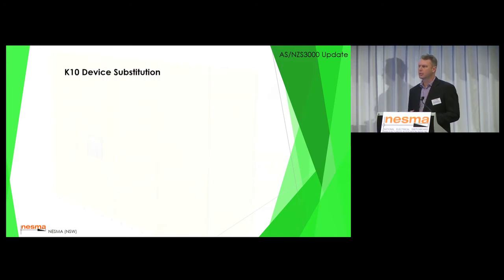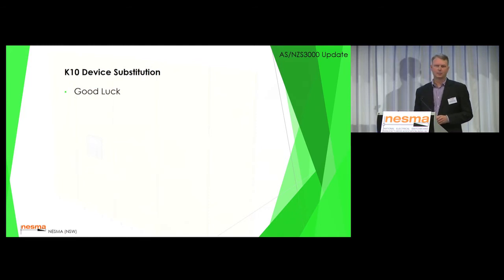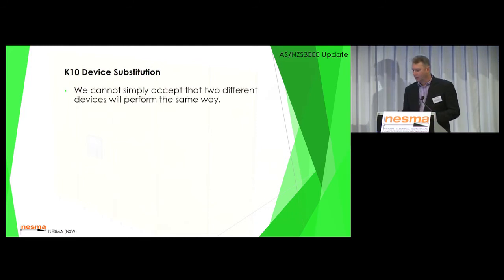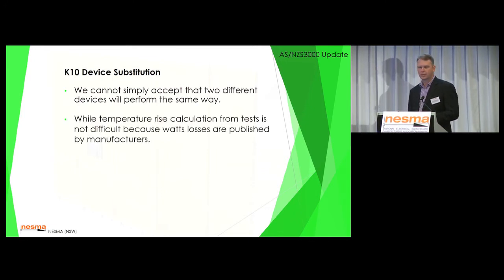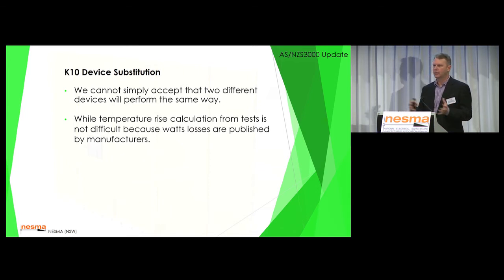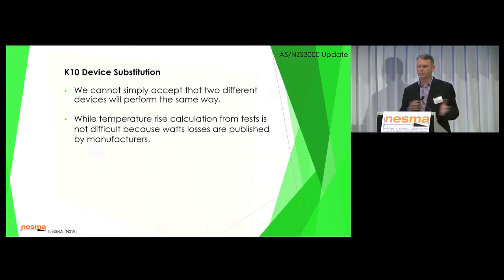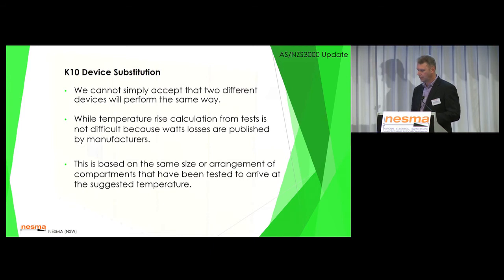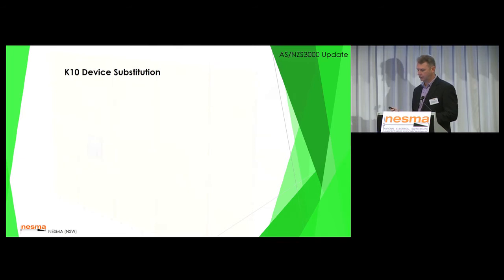Device substitution. Now this is a hot topic that's gone backwards and forwards in the 61439 committee for several days. Good luck is the beginning of that one. We cannot simply accept that two different devices will perform the same way. While temperature rise calculations from test is not difficult because most manufacturers provide watts losses from each circuit breaker, so it's quite easy to say that this one has a lower watts loss. We can position that in the same way and accept that our temperature rise is going to be acceptable. It's based on the same size or arrangement of compartments that have been tested to arrive at that original temperature.